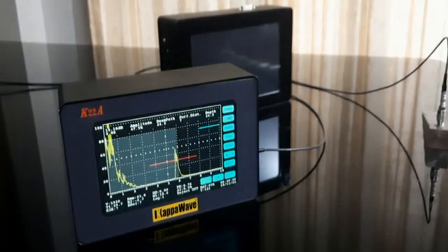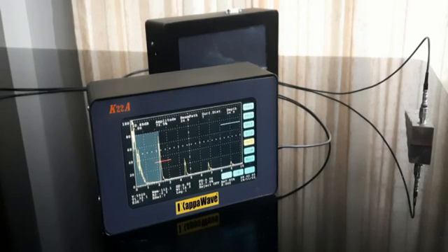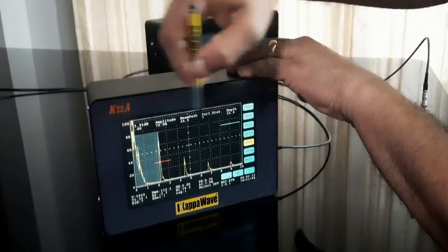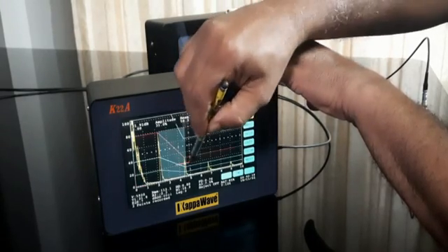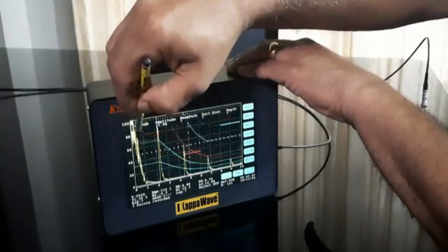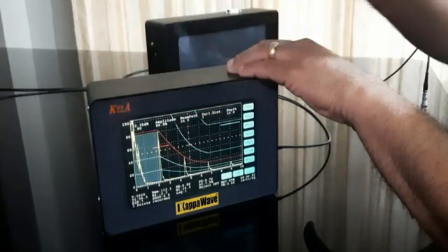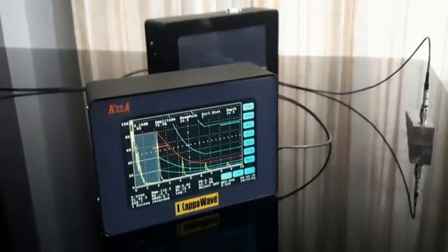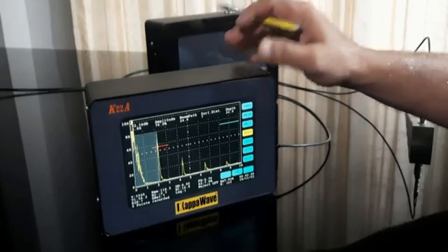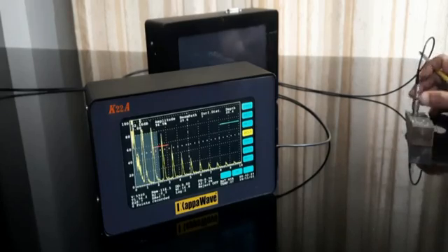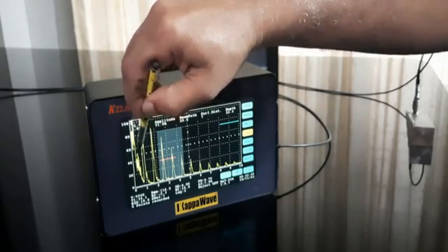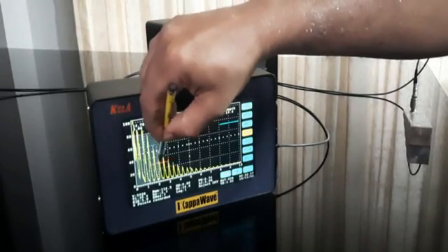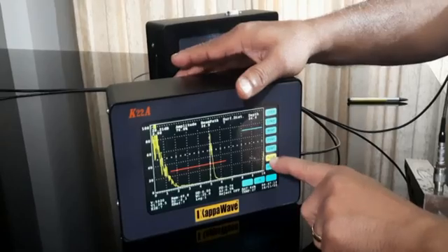Just like K8 and K8 LTD, this becomes fairly easy to use. A DAC is being constructed. Gate may be extended to cross two indications for an echo to echo value. This shows 10 millimeter thickness. On the step block, this is 5 millimeters thickness. With normal beam probe, you can measure as low as 1 millimeter easily.